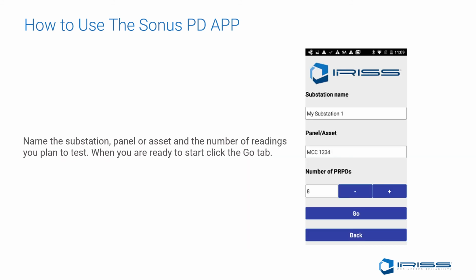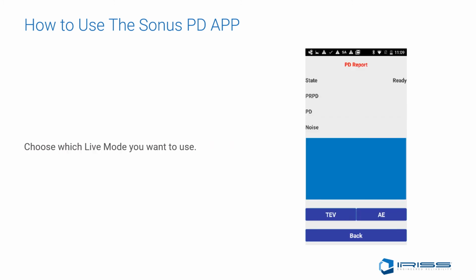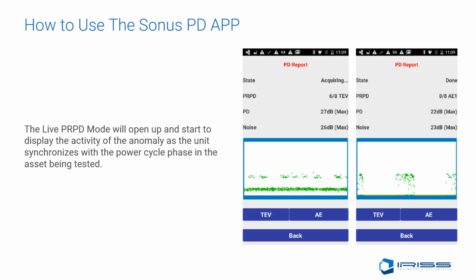The next screen will allow you to name the substation, panel, or assets and the number of readings you plan to test. When you're ready to start, click the Go tab. This will launch you to the reading screen, where you'll be able to see either the live mode in TEV, AE, HFCT, or UHF. Once you've selected your mode, the live PRPD mode will open up and start to display the activity of the anomaly. As the unit synchronizes with the power cycle phase in the asset being tested, it will start to display a scatter plot.